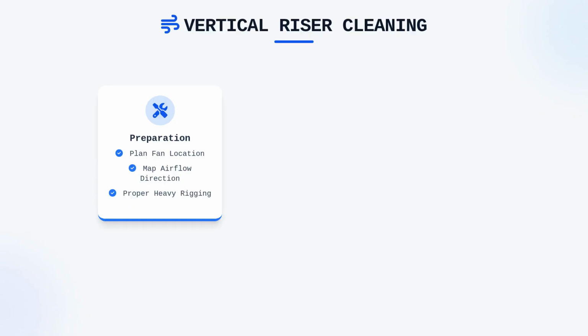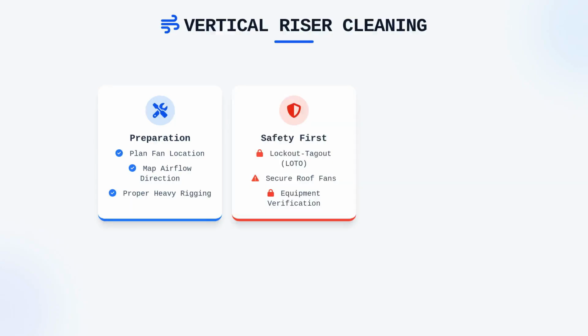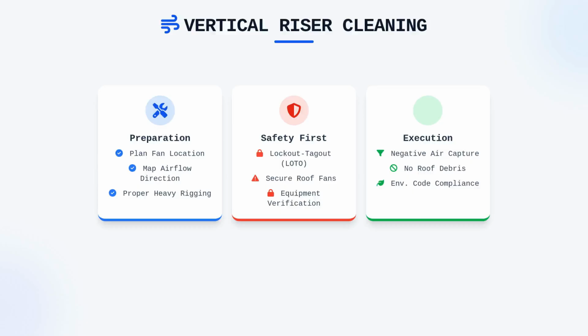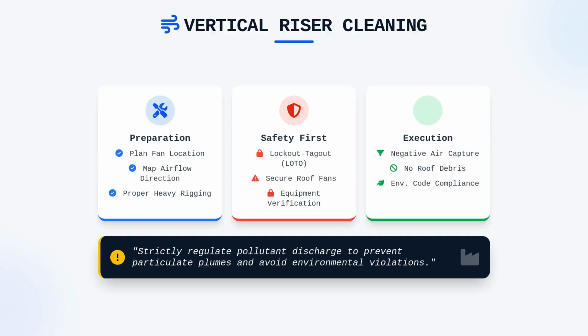You should always secure the fan via lockout tagout procedures before inserting any brush or vacuum equipment into the riser. During the process, ensure that your negative air machines are positioned to capture any dislodged debris, preventing it from being blown out of the exhaust stack onto the roof surface or into neighboring intakes. The discharge of exhausted air pollutants is strictly regulated, and you must ensure your cleaning process does not create a plume of particulate that violates local environmental codes.